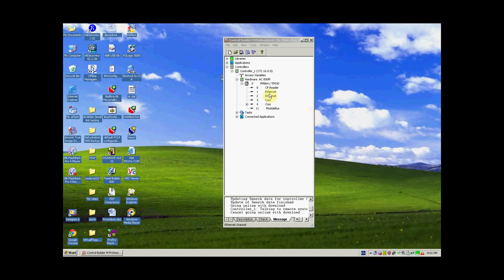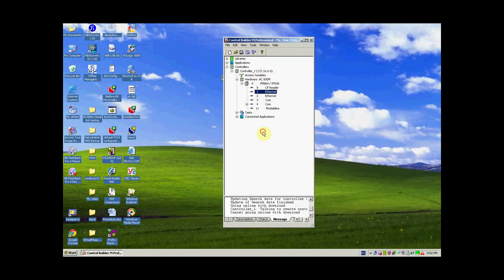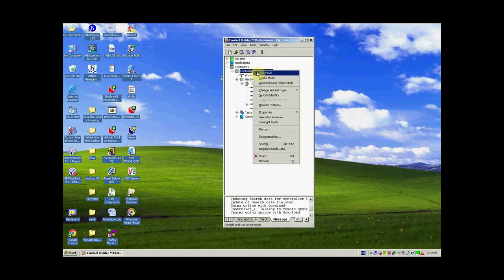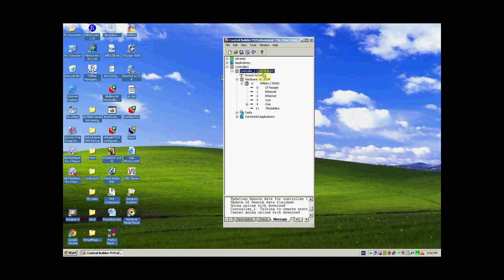Now go to Control Builder Professional. CN1 and CN2 are the two ethernet ports on the AC800M PM864 controller. Right click on Ethernet 1 and go to Editor. Introduce the IP address 172.16.8.55 with subnet mask 255.255.255.0. Click Save and Exit. Similarly, right click on the controller, click System Identity, and select 172.16.8.55. Our controller is now set to 172.16.8.55, assigned to CN1.